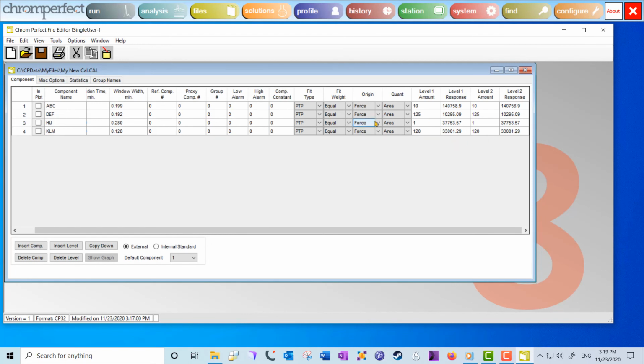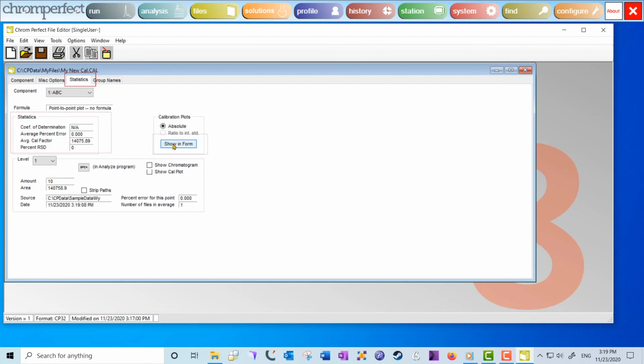You may remember in an earlier section, we discussed the calibration replace and calibration average options. This was on the instrument download form in the Run program. When running samples, you can choose these options to automatically update your cal file by indicating the level that will be updated. Look on the Statistics tab for important measurements about how well your data fits your calibration curve.